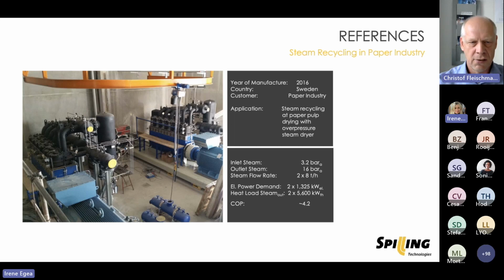And so this complete drying process is more or less self-supplying. The only energy input is the electrical power demand of these two compressors. With this compression from 3 to 16 bar, it's about a factor of 5 compression ratio. We reach here a COP factor of about 4.2. Next slide, please.